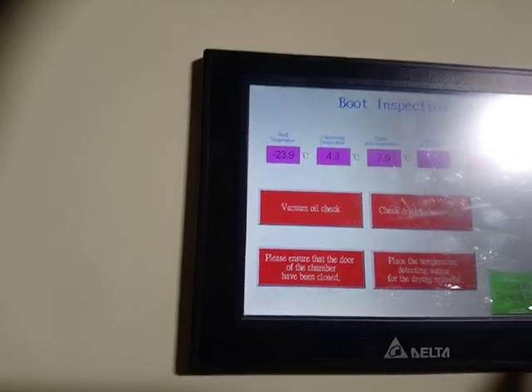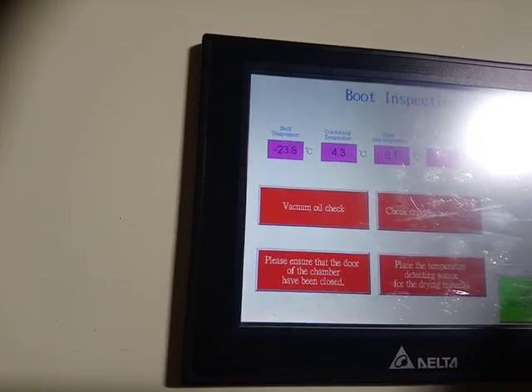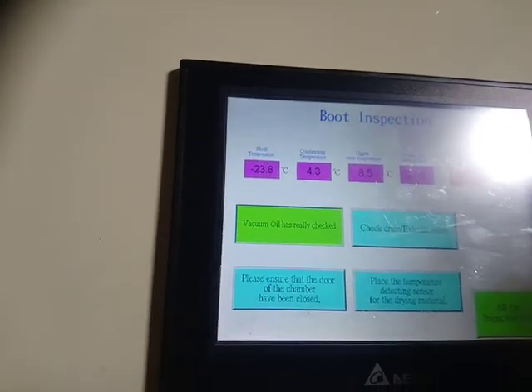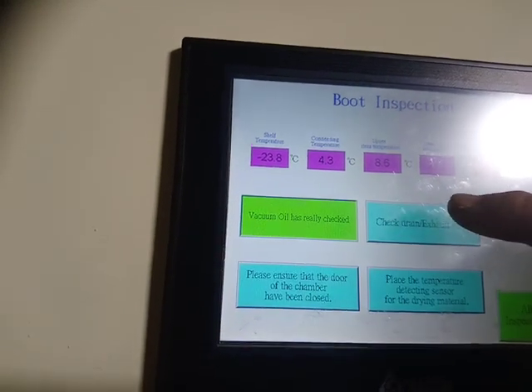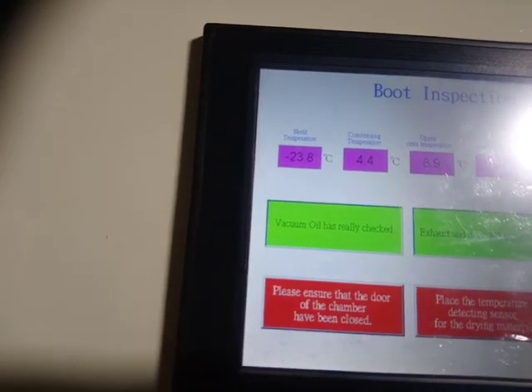Then we go to the inspection. Here there are 4 items to pay attention to. Vacuum oil check, and check the drain and the exhaust valve. Here are the drain and exhaust valve. This is a drain valve, or the extracting valve. If you want to start the machine, you should lock the valve.